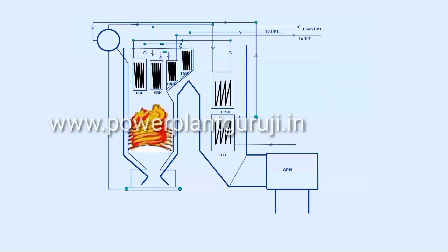Let us take a look at the standard pulverized coal-fired boiler of 500 megawatt or 800 megawatt unit. If I take a look at the temperature profile across the furnace as well as the second pass, the furnace temperature will be in the range of around 1,200 to 1,400 degree centigrade. Then when it reaches the platen superheater region, the temperature goes to around 1,000 degree centigrade, 950 and so.